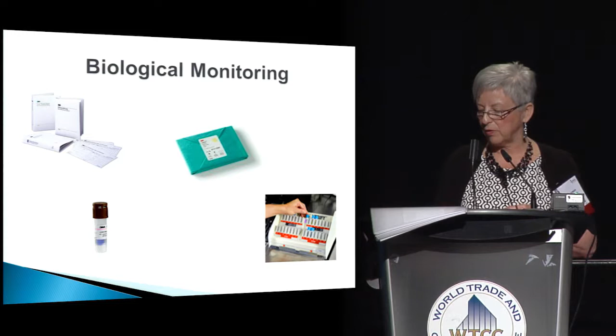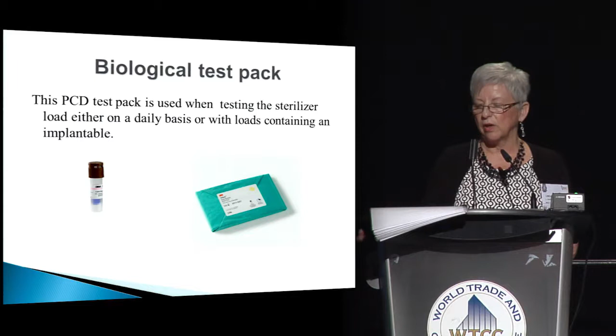So again, there's more things to consider when you're purchasing your BIs, and refer to the standards for that. So a BI is just a little vial that holds the BI. A process challenge pack comes in many different forms. It has the BI and it would have a different type of chemical indicator with it. A biological test pack is usually what's used. That's tested daily in the sterilizers and whenever an implant is used on a daily basis. And all this monitoring is documented within departments.